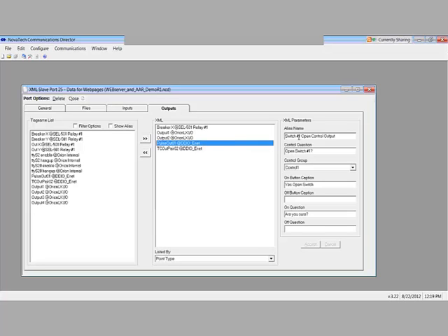So here's the alias name that I defined earlier. Here's the control question, open switch number 1. The control group says who is allowed to control items on the web page. In other words, which users have the privilege to perform this control action. You set which control group is able to have the permission to control this particular element.